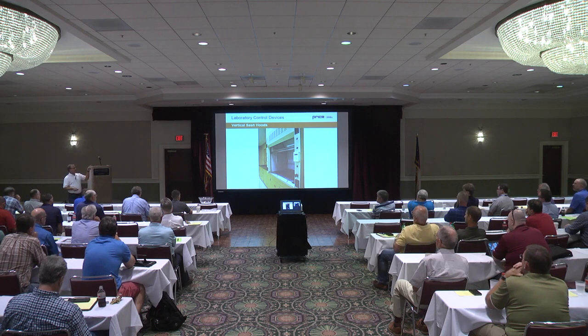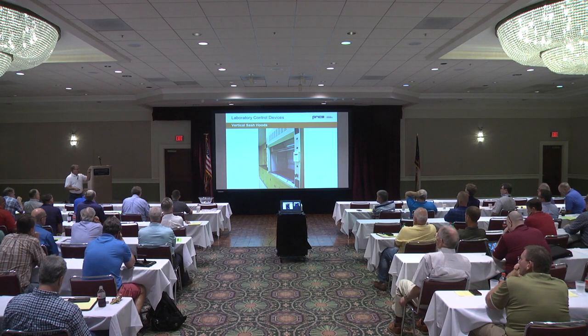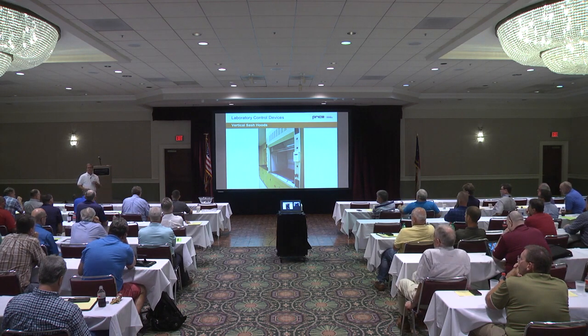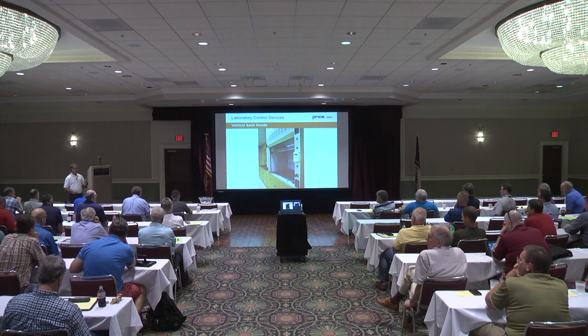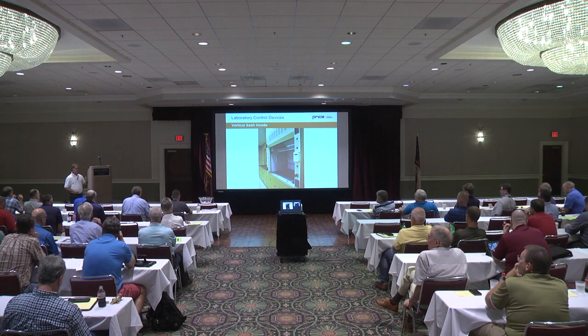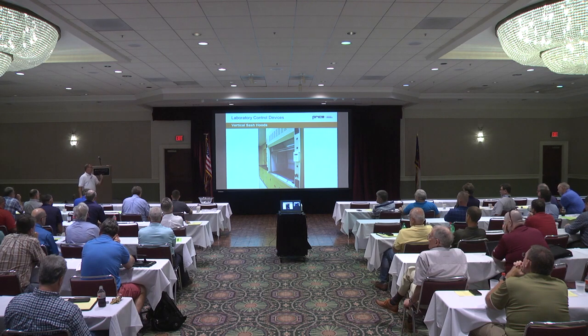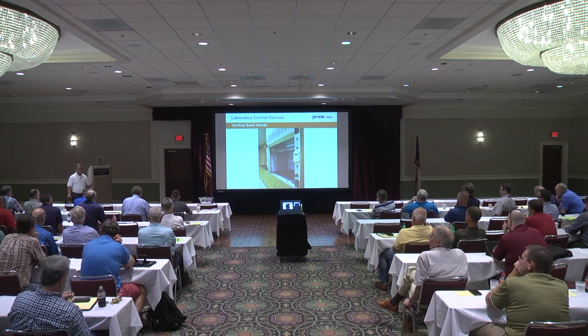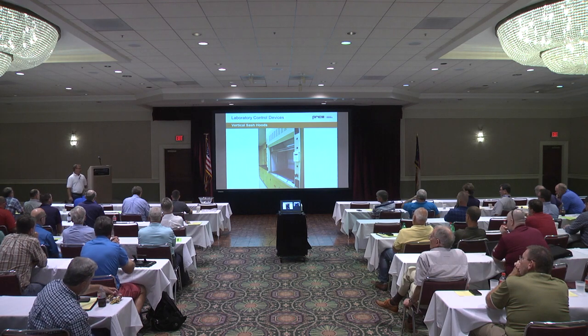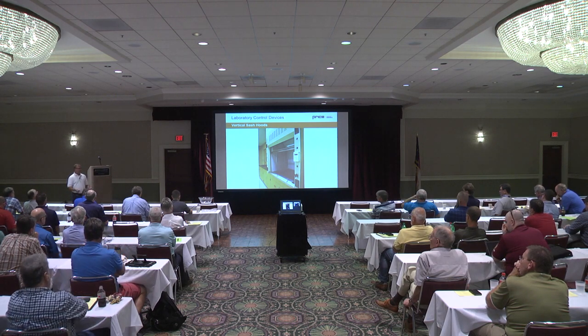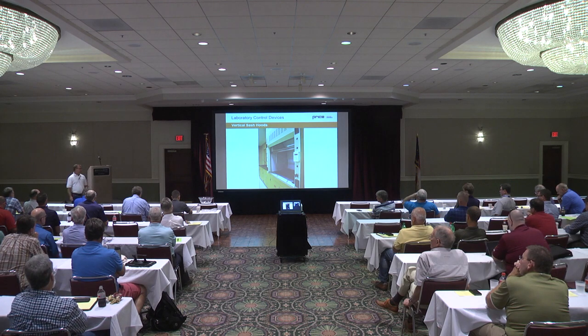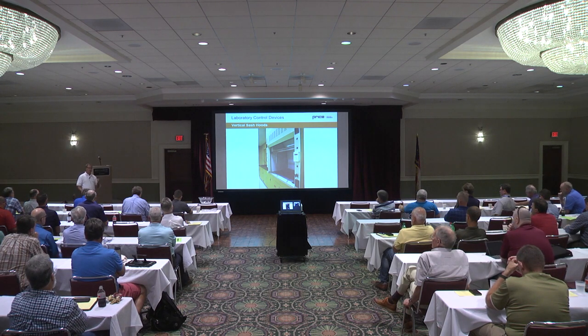We don't account for the louvers initially, but I have seen cases where the louvers did have enough air going through them when the sash is open to prevent the velocity at the face of the hood that we're all looking for. So then we have to back up and add leakage, or lower the sash for a lower sash height. You've got to do something to make the fume hood work, because we're not going to get a different fume hood at this stage. We've got the job, what we got.